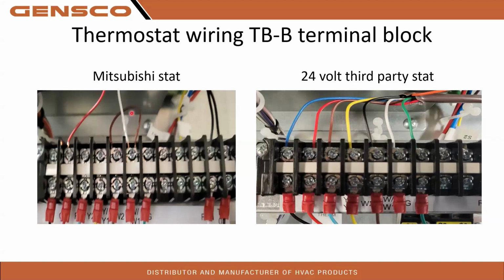By the way, make sure you're putting this on the TBB terminal block. I've seen guys hook this up to TBA and the homeowner has the system shut off and it's suddenly maintaining 65. They can't figure out why. It's because this thermostat's controlling the gas furnace and telling it to come on. So make sure it's on TBB. That way it's going through the relay board and only working when it's supposed to.